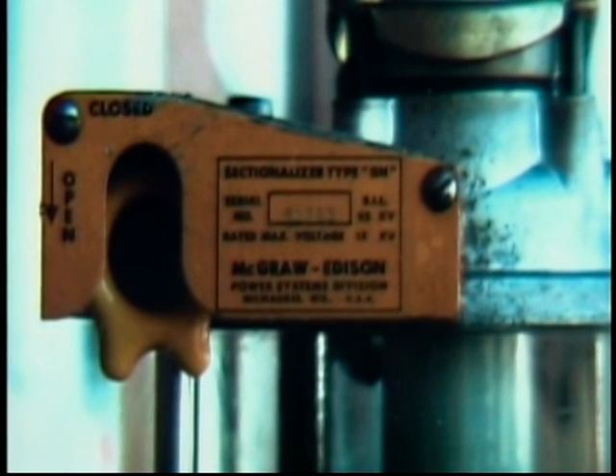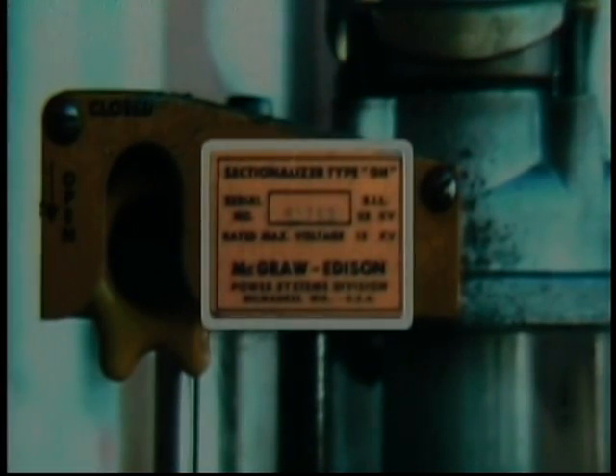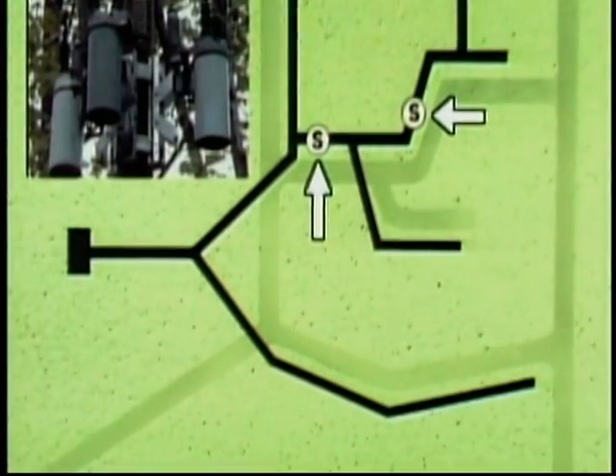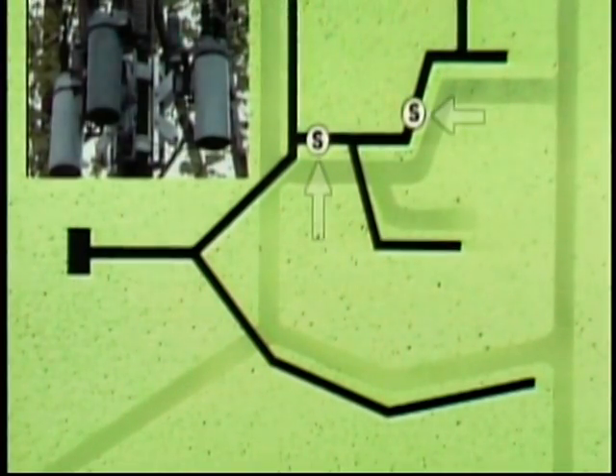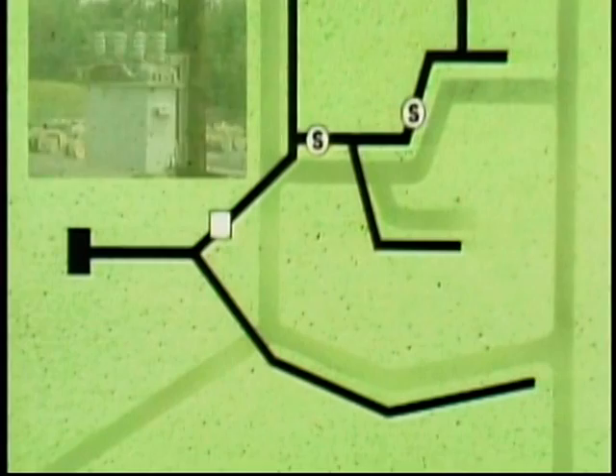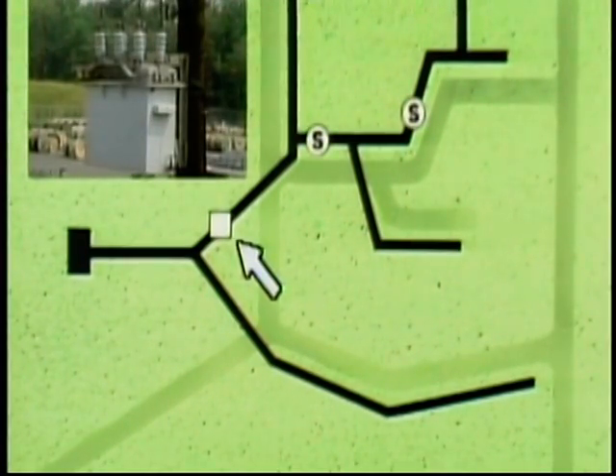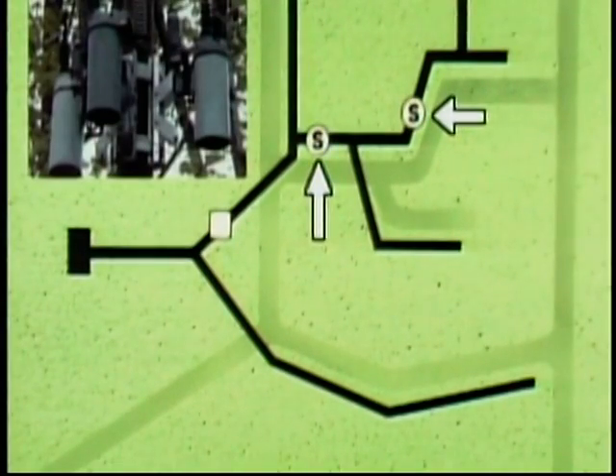However, it's not always possible to tell a sectionalizer from a recloser by its size. Sometimes the only way to be sure is by looking at their nameplates. Sectionalizers are commonly used where a lateral is tapped off a feeder or where a branch line is tapped off a lateral. They're also usually coordinated with reclosers or other protective devices. When a sectionalizer operates, it will typically disconnect a smaller portion of a circuit than is disconnected by a recloser.